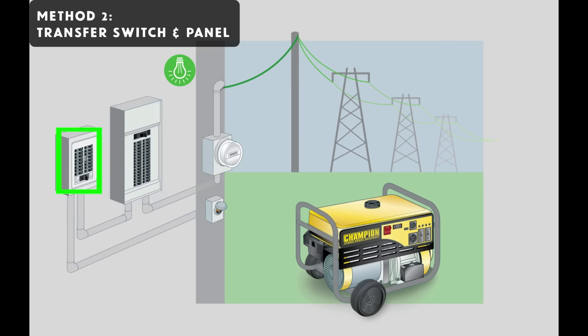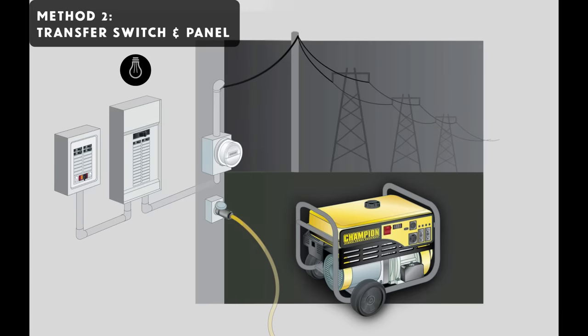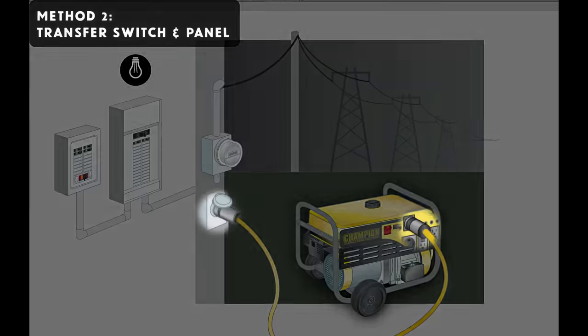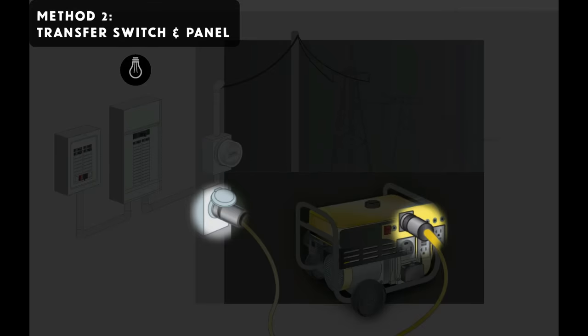All of the essentials would be relocated during installation from the main panel to this transfer panel. And with that in place, you're all set and ready to go in the event of an outage. When things go black, you're all set to do two things to get your generator powering your home with this transfer switch situation. The first thing you need to do is to connect the generator and the outdoor port with a special cable that's meant to do this. It can handle all the power the generator puts out, and it has the appropriate ends.